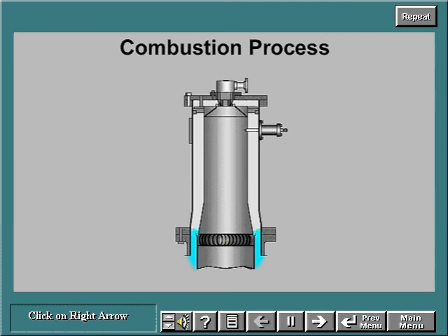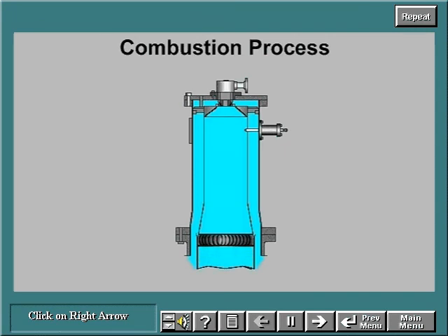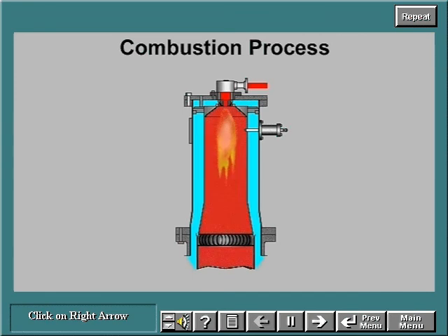The combustion process works like this: compressor discharge air flows through the annulus between the outer casing and the liner and enters the liner cap. Fuel is injected into the liner cap and mixes with the compressor discharge air. The fuel-air mixture is ignited by the spark plug. The hot and rapidly expanding combustion gases then flow to the first-stage nozzles in the high-pressure turbine section. Once ignited, the combustion process is self-sustaining as long as fuel and air are available.